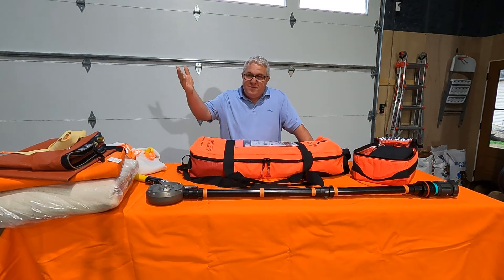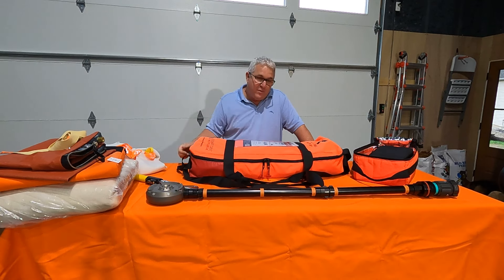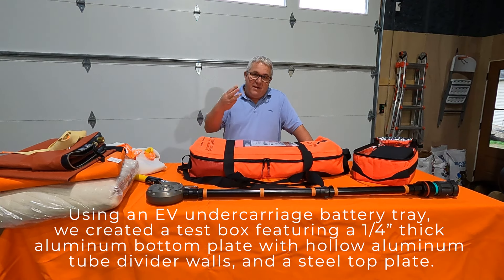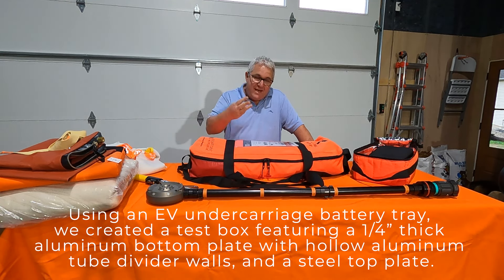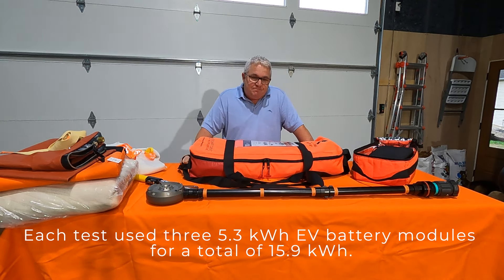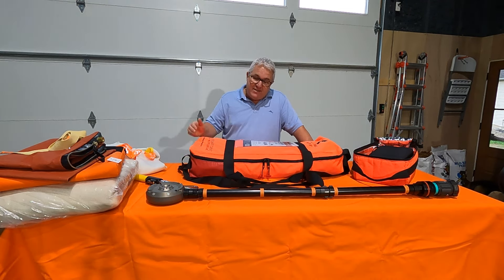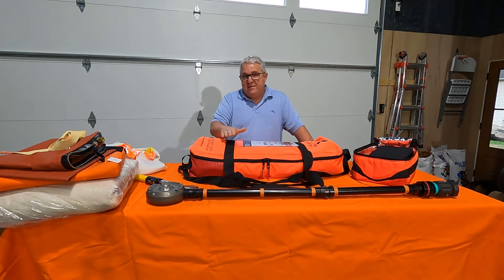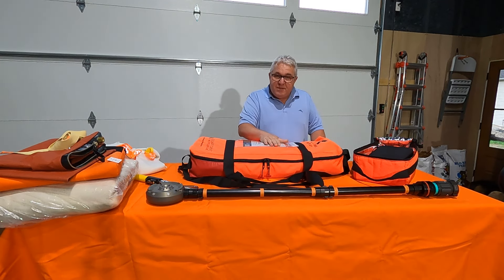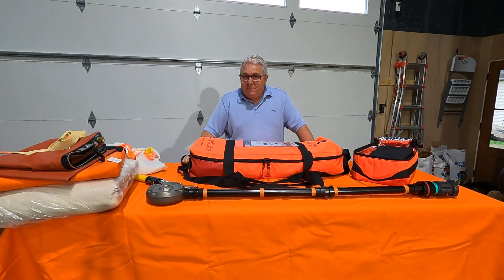What we learned at the third-party facility we use — run by a 30-year firefighter and other firefighters who work with him — they did a series of tests for us. We did seven Tesla S-module tests equaling almost 16 kilowatt hours in a Tesla S-bed. We did tests with no response, a couple with blanket-only, and a couple with blanket and our water mister. We've got really great data.